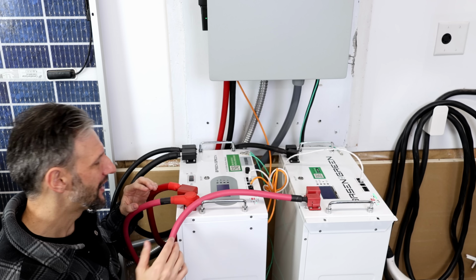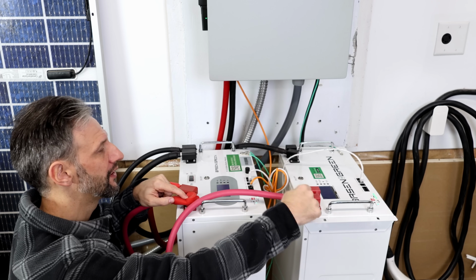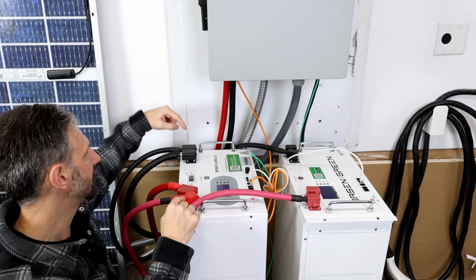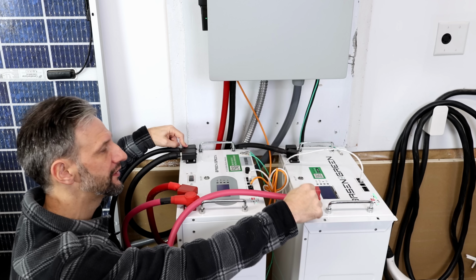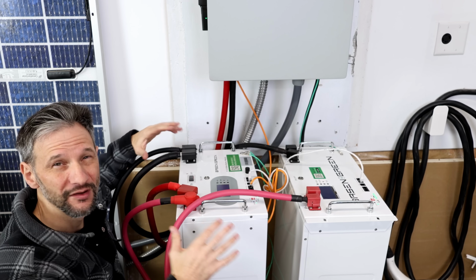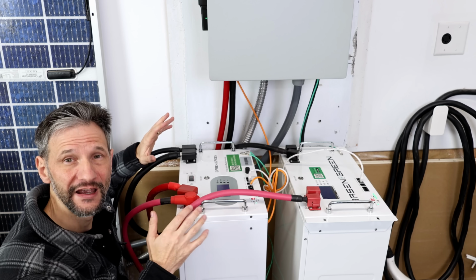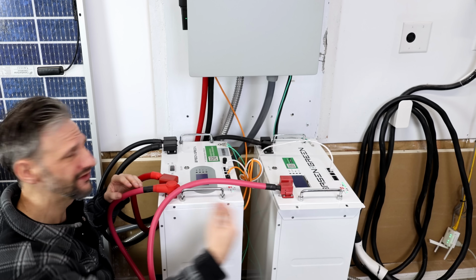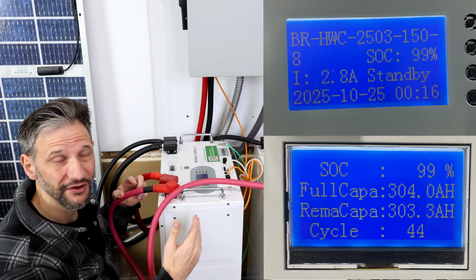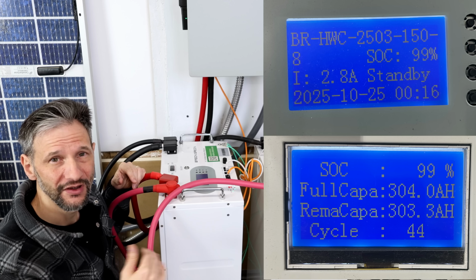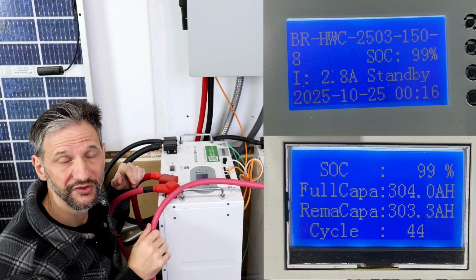Ideally, I would have short 4-aught cables connecting these in parallel, and I would take the negative from one battery and the positive from the other battery, which would balance them even more. But even in its current configuration, they stay within 1 or 2% of each other, and when they charge all the way to the top, they both hit 99 to 100%, no problem.